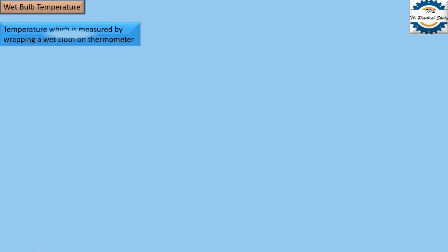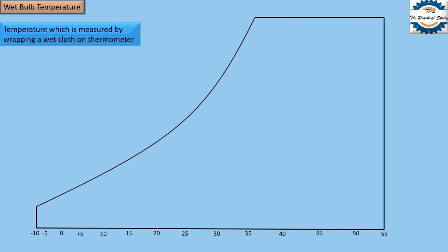Wet bulb temperature is the temperature measured by wrapping a wet cloth on a thermometer. We have already made a video on this topic. On the psychrometric chart, the wet bulb temperature lines are inclined at an angle of around 25 to 30 degrees, and the wet bulb measurement scale is shown along the saturation curve.